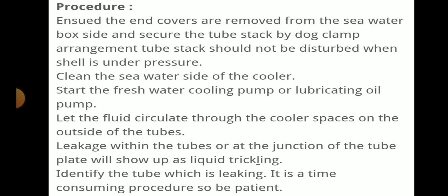The tube stack should not be disturbed when the shell is under pressure. Then clean the seawater side of the cooler. Start the freshwater cooling pump or lubricating oil pump. Let the fluid circulate through the cooler space on the outside of the tubes.